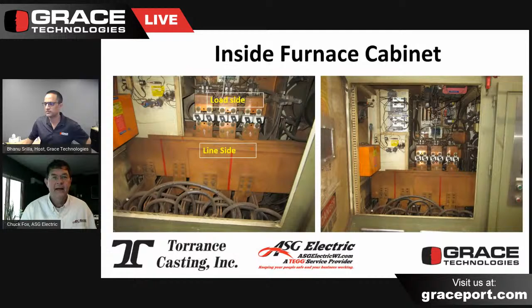As we take a look at that, all of this line side busing is in the foreground of the cabinet. So from a worker perspective, if you open up this cabinet door and you're making an assessment that that line side busing is indeed de-energized, it's the first thing that greets you as you go into this particular design of the cabinet. So to be absolutely sure that we had zero energy on the line side, one of the concerns the plant manager brought up is for some unlikely reason, we lose all of the fuses at the same time.